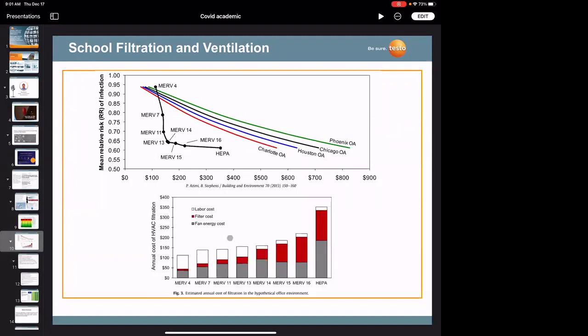But when you look at the actual fan power cost, and this is what I think the question was getting to, it's going to destroy our systems, it's going to cost too much, the pressure drop's too great. Today's MERV 13 filters, you can buy a number of MERV 13 filters that require less than a 0.2 inch pressure drop across it. As a matter of fact, some are down to 0.16 inches. And the only thing that you want to do when you put in a MERV 13 filter is you need to just check it more often, obviously, because you're going to have either a 2 or 4, maybe even a box filter, depending upon the ability of your system.